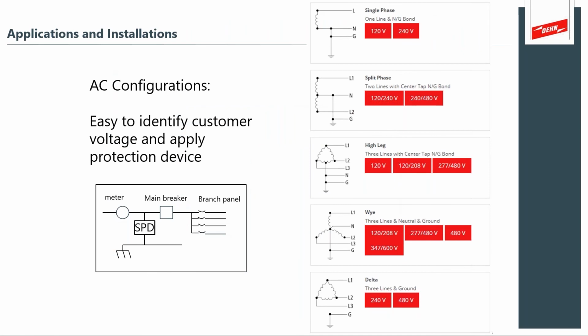So AC power protection comes in many flavors. DEHN is happy to provide a configurator on our website where you can easily find your electrical voltage and then get to the SPD type of a device suitable for your electrical power configuration. And what's important on this slide is showing that you want to place your very first important SPD right in front of your main system to provide the most effective control of your electrical power. But remember, in a system, there may be branch circuits that are also delicate, and you want to have SPD devices perhaps downstream from your main.